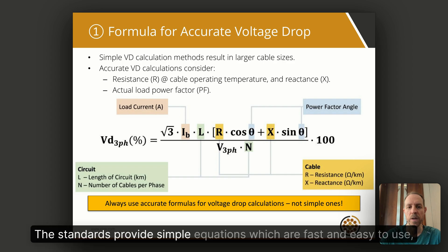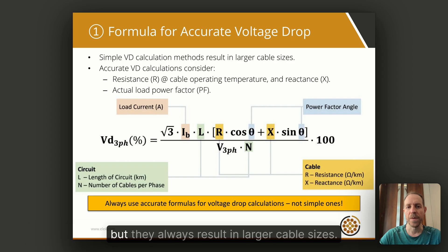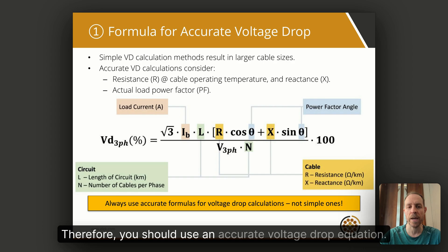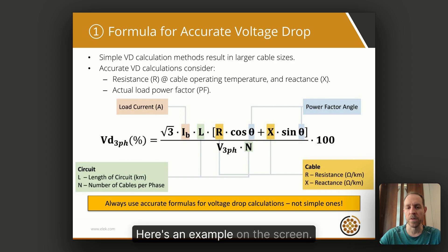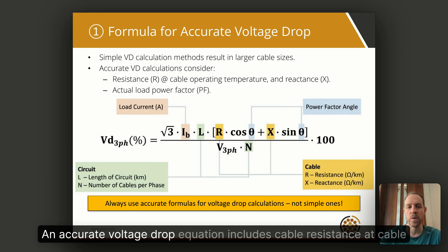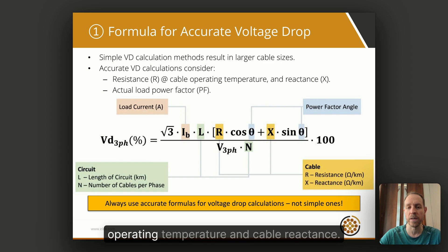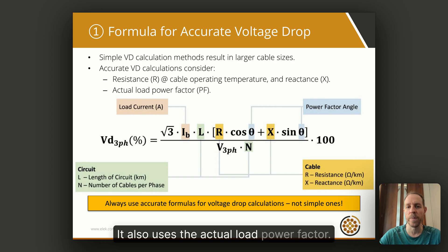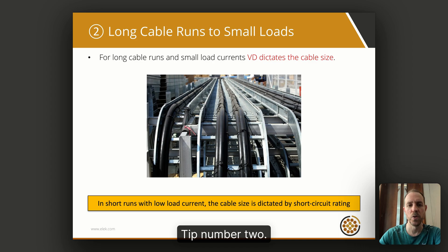Tip number one: use an accurate formula for voltage drop calculations. The standards provide simple equations which are fast and easy to use, but they always result in larger cable sizes. Therefore, you should use an accurate voltage drop equation. An accurate voltage drop equation includes cable resistance at cable operating temperature and cable reactance. It also uses the actual load power factor.